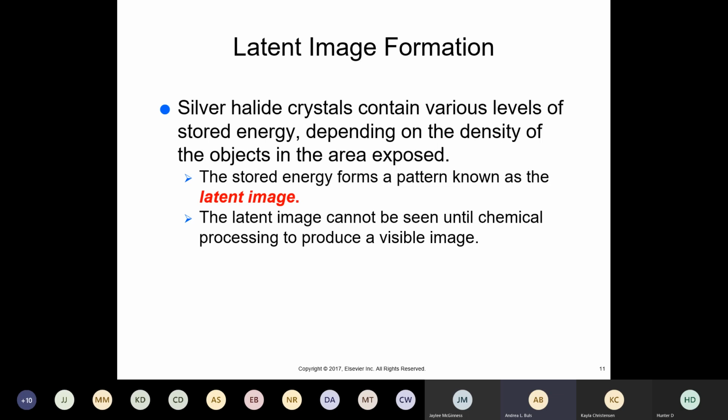The amalgam is going to absorb it all, so none of that X-ray is going to hit a silver halide crystal. Some of it will hit the enamel of my tooth, which is going to absorb an awful lot of it, but a little is going to go through. And then some of it's going to hit my soft tissue, which is going to let a lot more through, which is going to give its energy to those silver halide crystals. So now I have that latent image on that film, which will be seen when it's chemically processed.